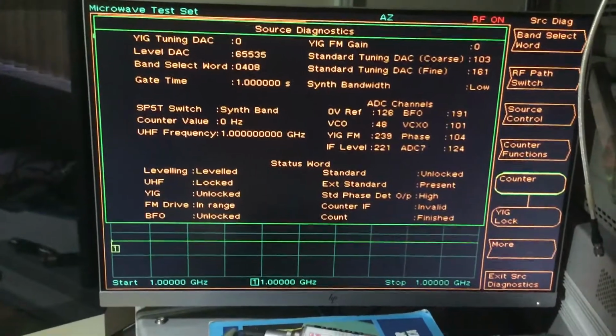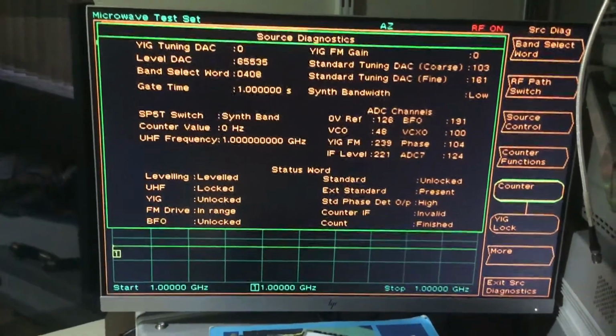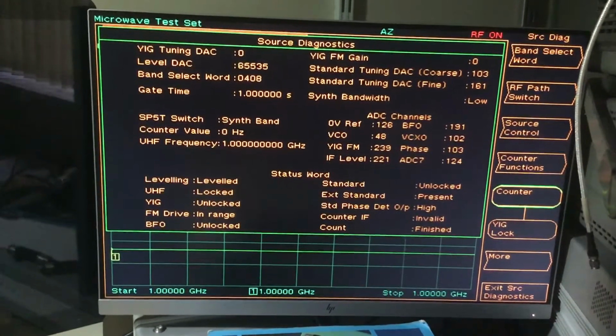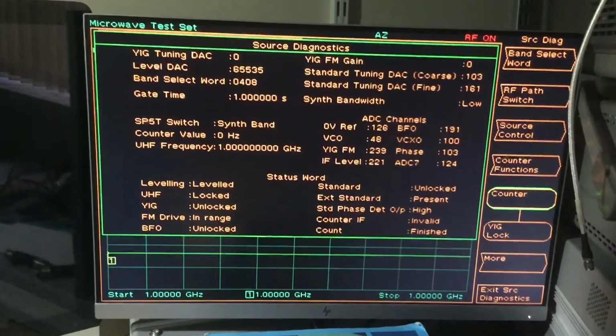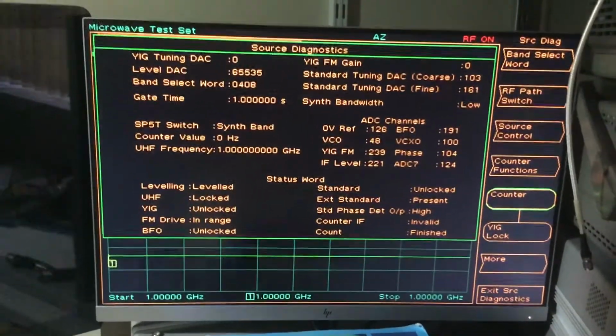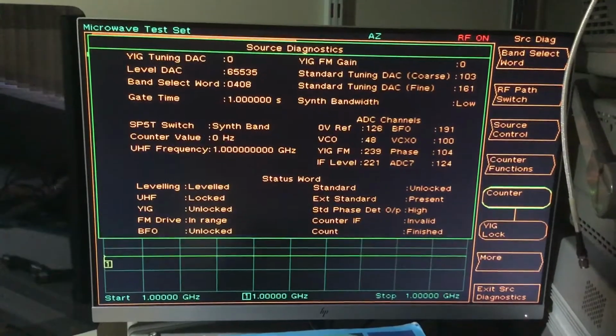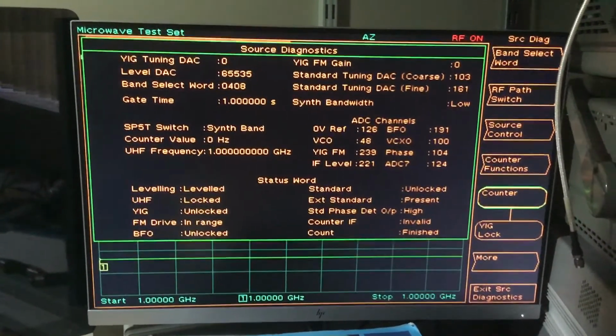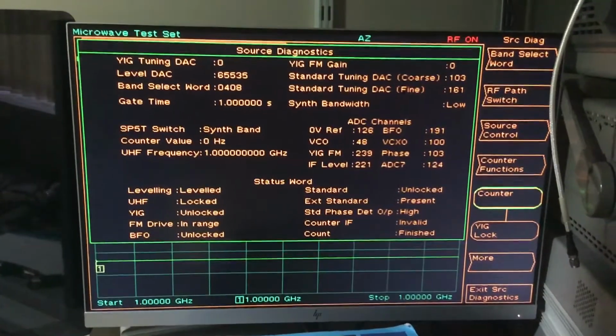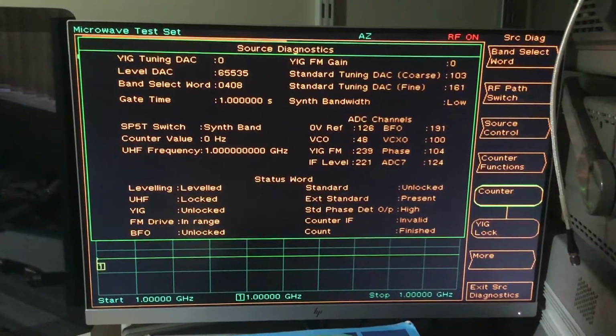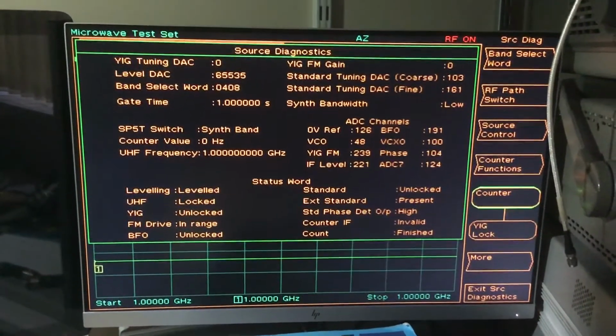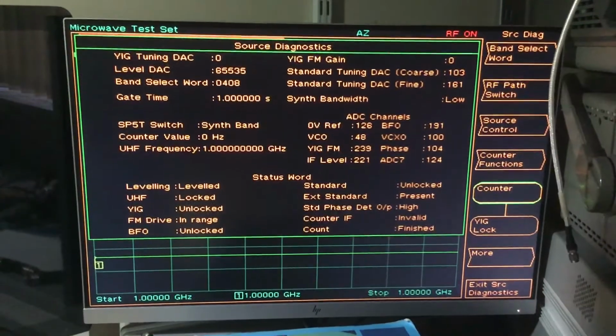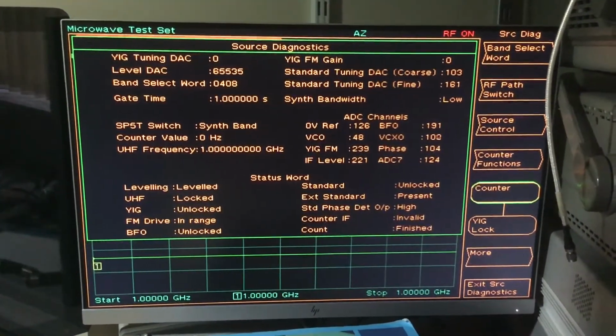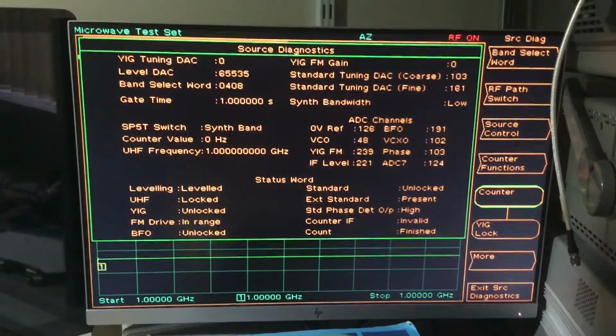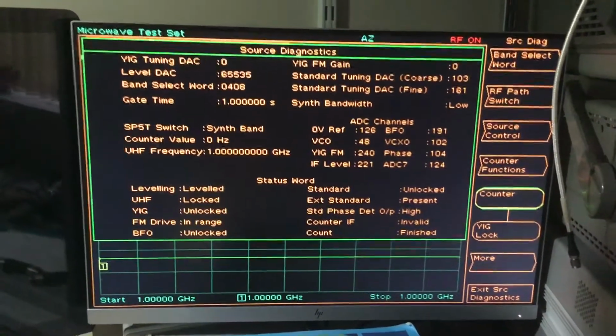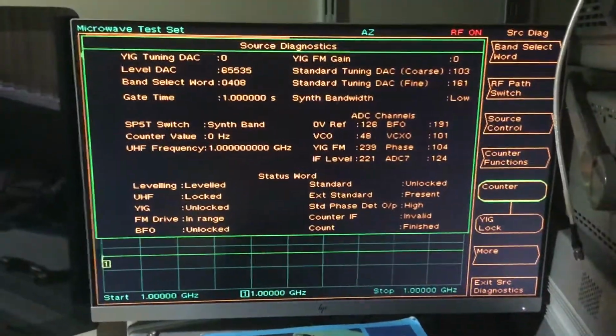It does multiple frequencies from 10 megs to 20 gigahertz, and it measures across its entire dynamic range in 1 dB steps. So it goes from the absolute minimum value up to the absolute maximum value of the RF output in 1 dB steps. Once it has attained each level from the RF output and measured it, it knows that's the DAC value that represents that RF level, and saves it into its calibrations memory. Then it progresses to the next frequency and does the same again through the entire frequency range. So as you can understand, it can take quite a long time.